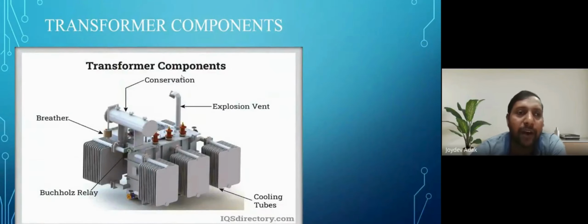So these are the different parts of the transformer. This is the main tank. This is the radiator bank for cooling of the transformer oil, and this is the Buchholz relay used between the main tank and the conservator tank. This is the silica gel breather, and this is the explosion vent. Normally for a small transformer we use an explosion vent, and for a large transformer we use a PRV, pressure relief device. This is the cooling tube. These are the fins, and totally it is called the radiator bank.